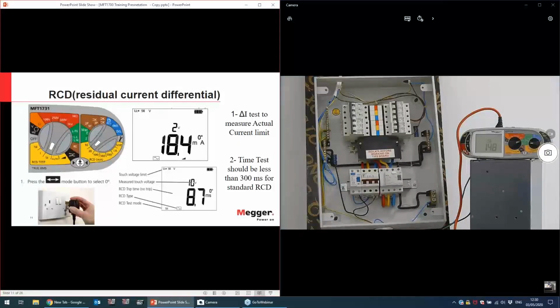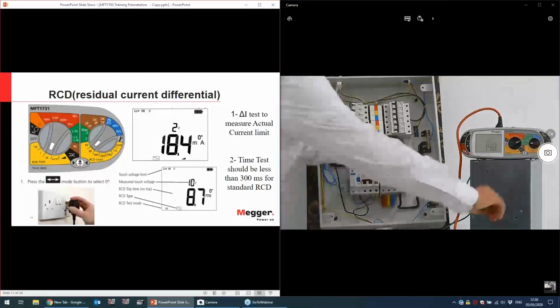Usually it's 10 to 30 milliampere. For us today, I got an even lower value, 10 milliampere, since my main distribution board inside my office is 30 milli. I don't want to use a similar value, so as not to trip that and lose connection to the internet. I will only be using 10 milli to do this test.